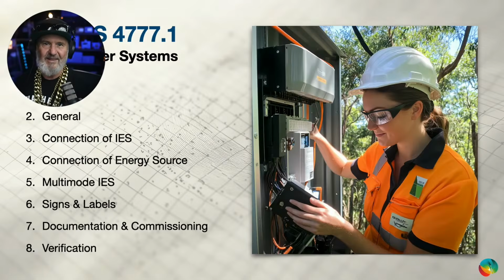That's great, so let's start on 4777 Part 1. What's changed? You always start with the scope to understand if you even need to comply with it. Then we'll talk about some general requirements, the connection requirements for inverters, which I should point out are now called IES - inverter energy systems - because there can be more than one inverter, and they may be part of a system, aggregated together. We'll explain some connection requirements, specifics around multi-mode inverters, your favourite topic, more signs and labels, because don't you feel safer the more you put up? No. And some documentation requirements.